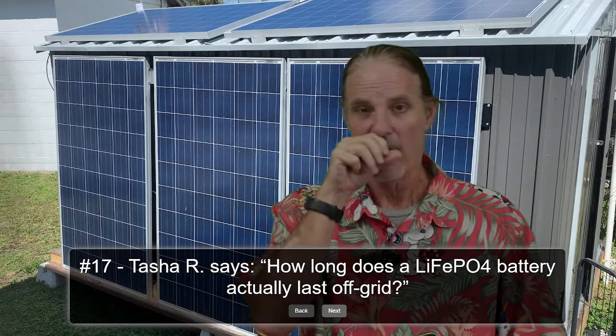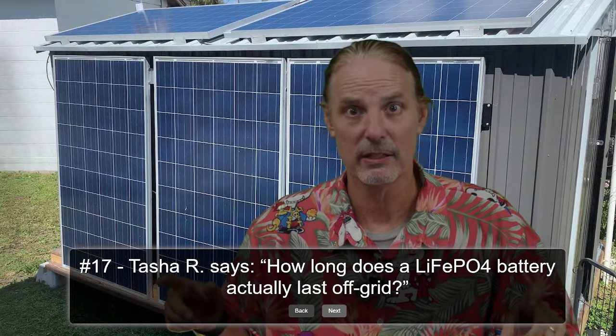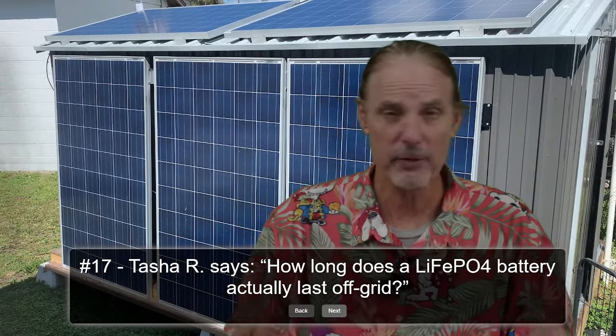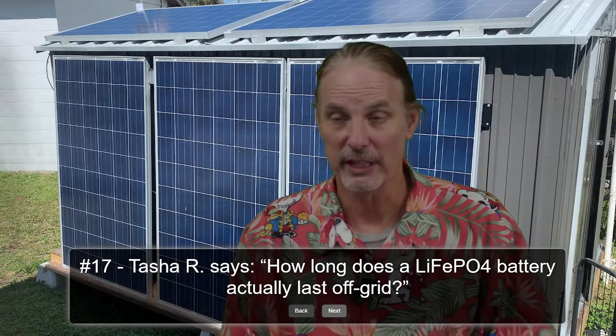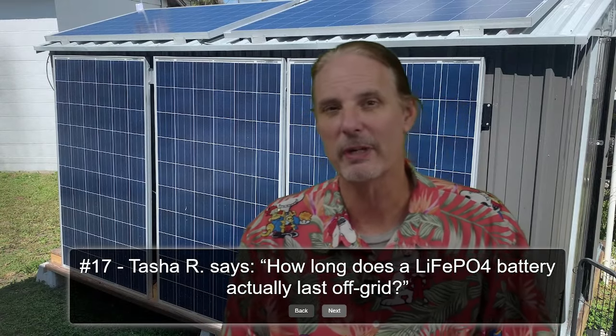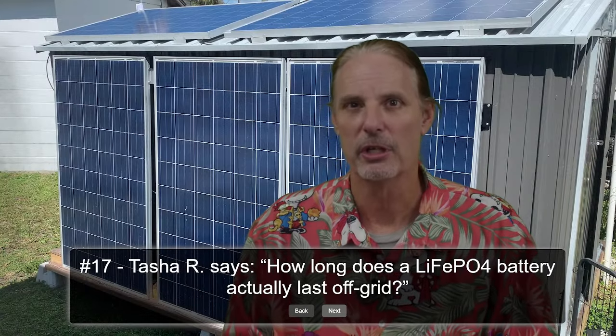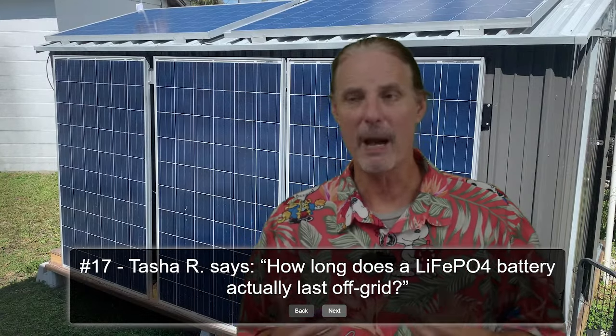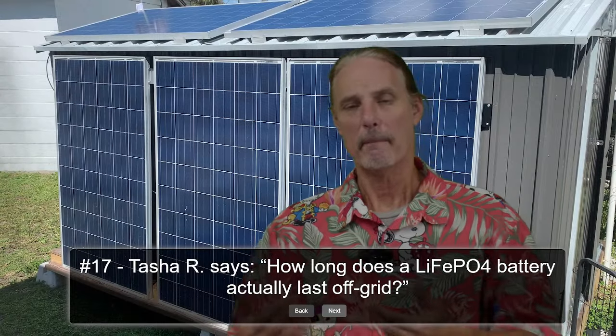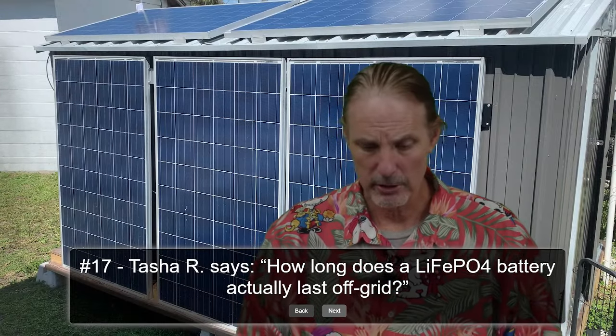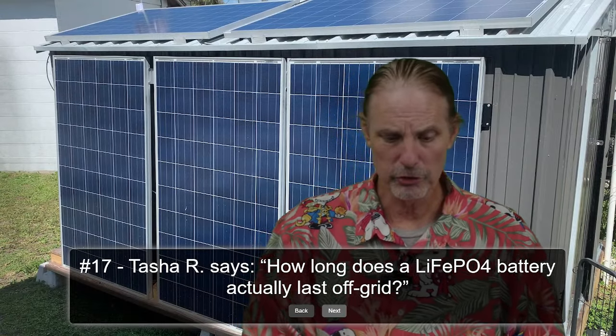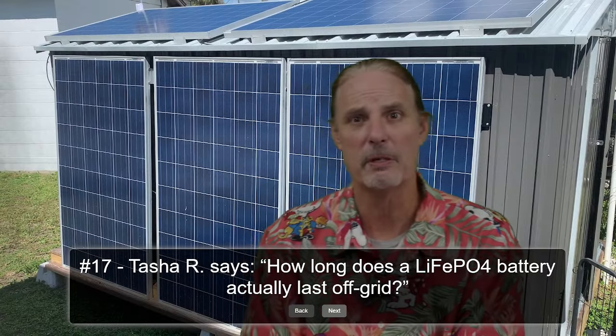Most of the batteries that are coming out claim to have 5,000, 6,000, 10,000, 12,000 cycles. The problem with this number is that nobody has defined what cycles mean, and every manufacturer defines it differently. Most of the time you don't know until you start reading the actual manufacturer definition of cycles. In my mind, a cycle means that I use a certain amount of the battery and charge it back up. I would probably say an 80% discharge and recharge should be 1 cycle.